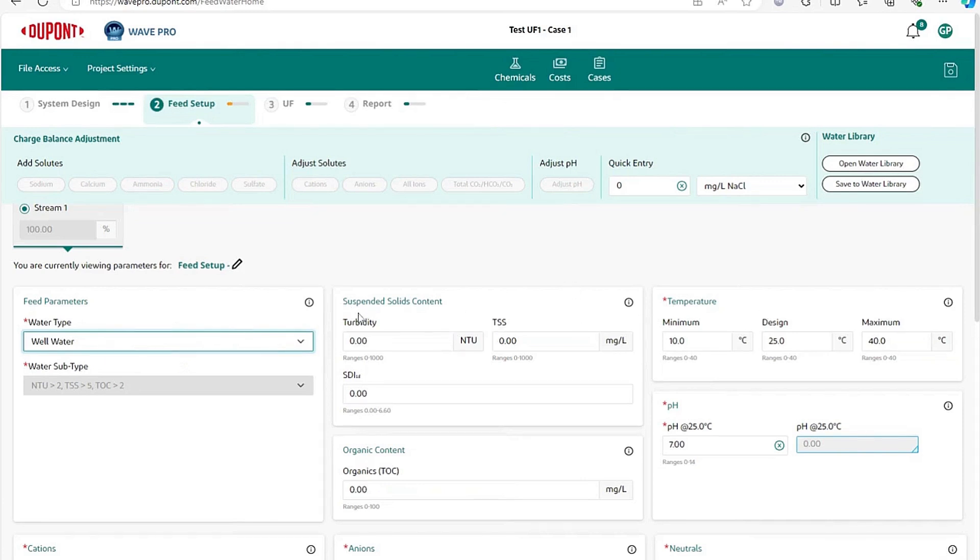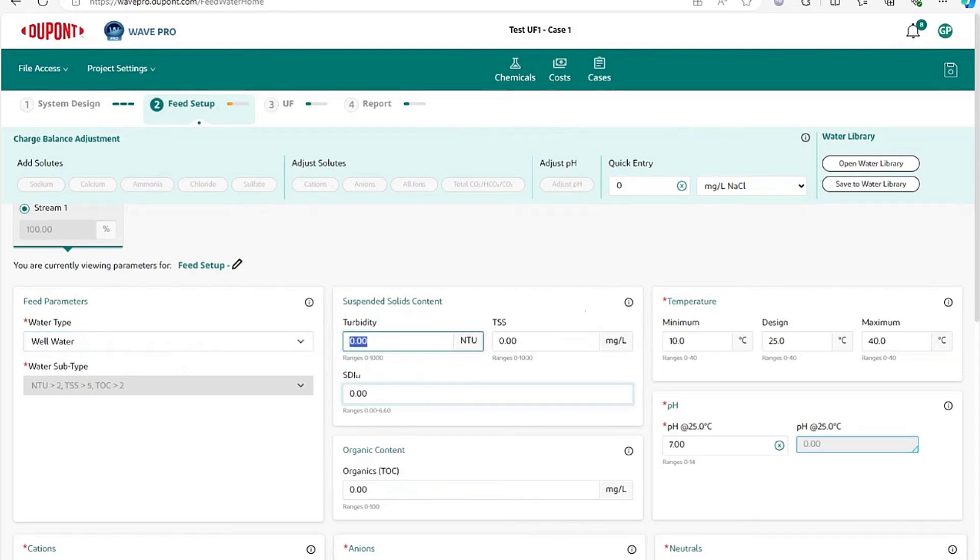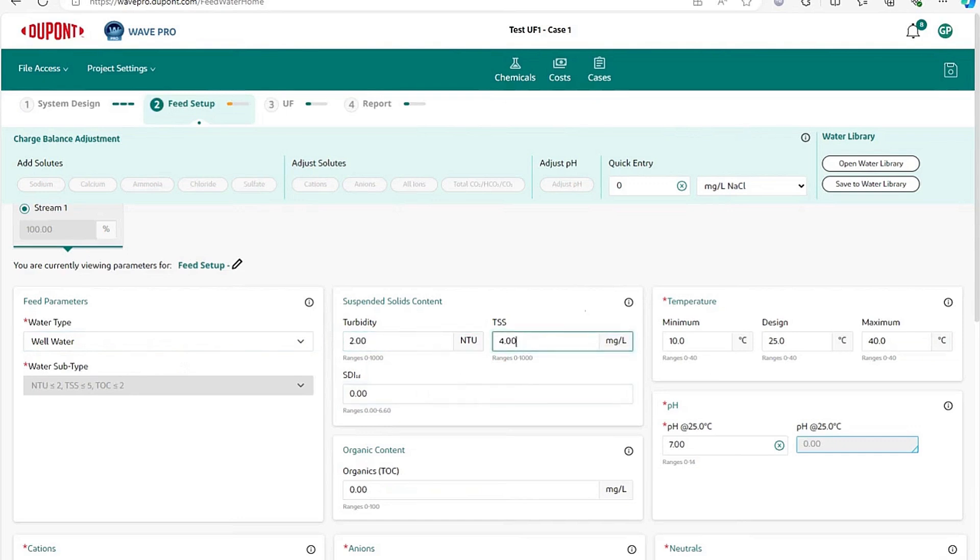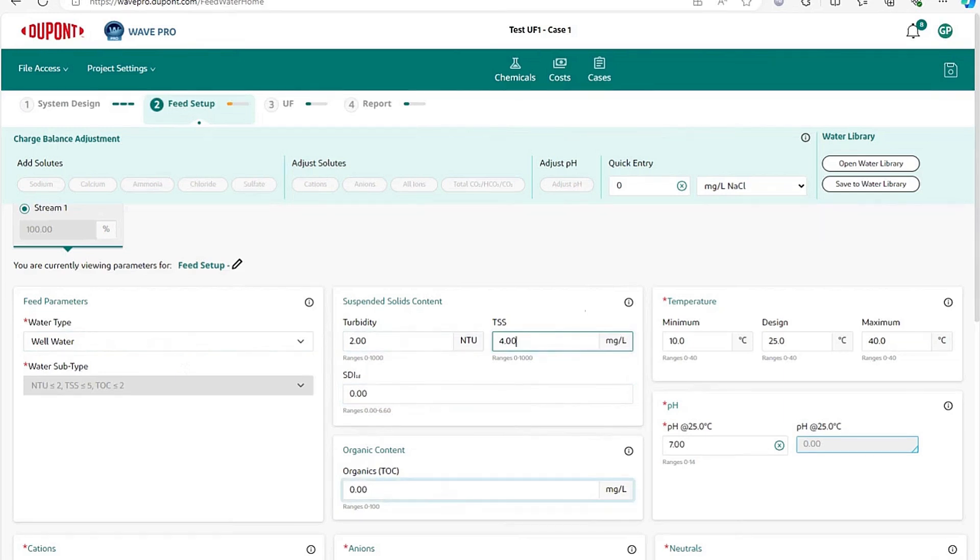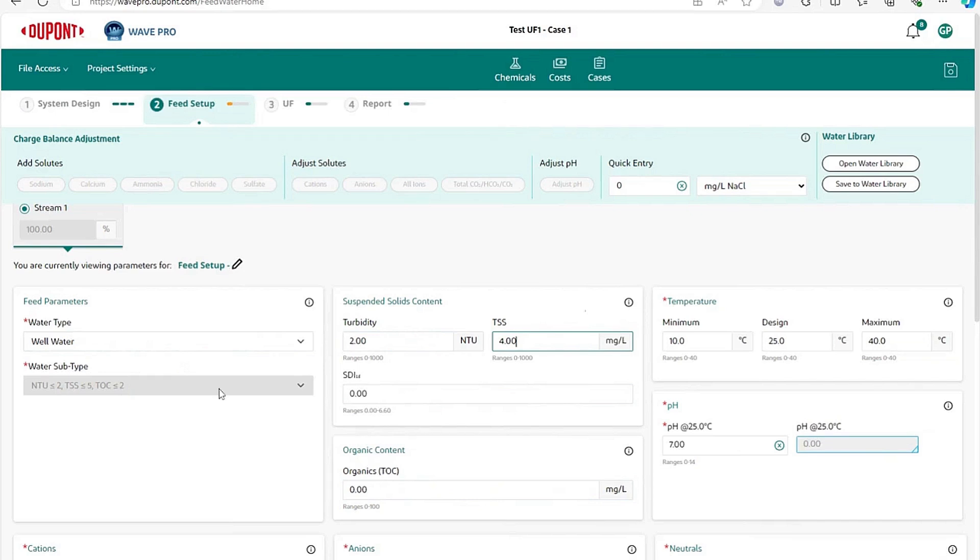The second thing you have to enter is what are your suspended solids. You can enter your turbidity, you could enter your TSS, you could enter your organics. These three values are important because they are used to pick what is called the water subtype, which would give you the exact design guidelines that will be used for your design.